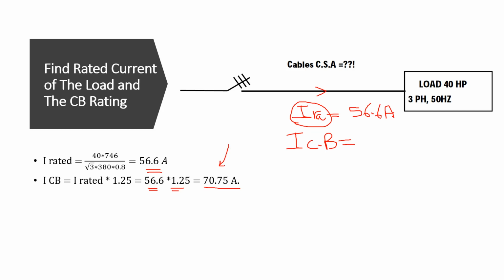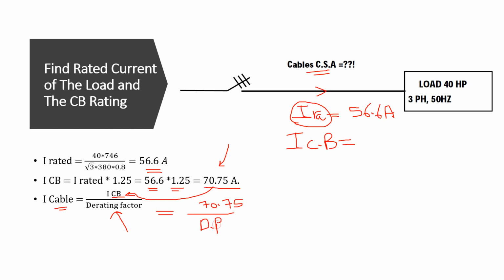Now we would like to get the cross-sectional area of the cable. In order to do this, we need to find the rated current of the cable itself. The rated current of the cable is equal to the circuit breaker current, 70.75, divided by a derating factor. The derating factor is the one which we would like to find. So the current we need for the cable is 70.75 divided by the derating factor. Now, how can we get this factor?